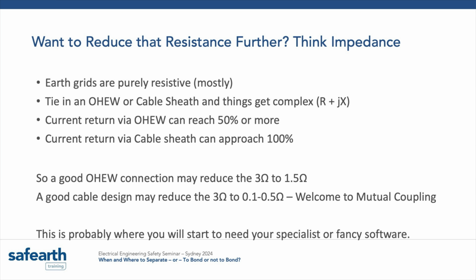So probably below us, or maybe just over there a little bit, not very far away, is Ausgrid's City Central New substation. It supplies 11 kV to most of this part of Sydney, and there's a couple of other ones on a 132 kV ring. The fault level's 50 kA now on that 132 kV system, and the substation footprint would be half the size of this room. And so you think to yourself, well, I told you earthing's a bad area.